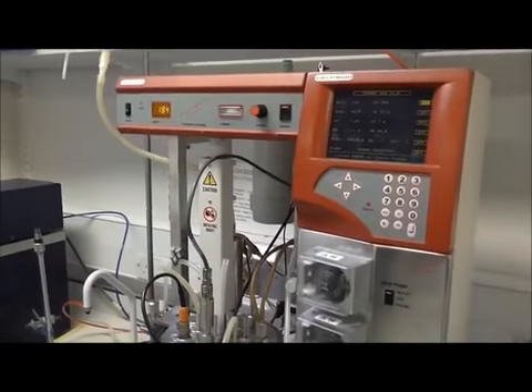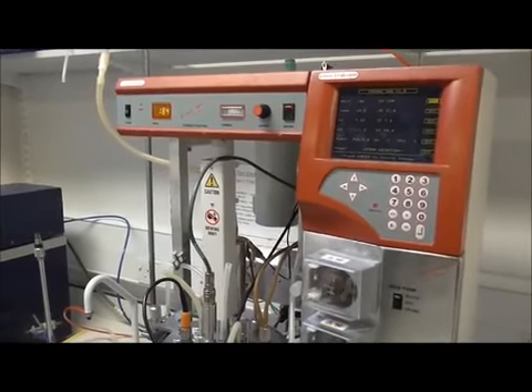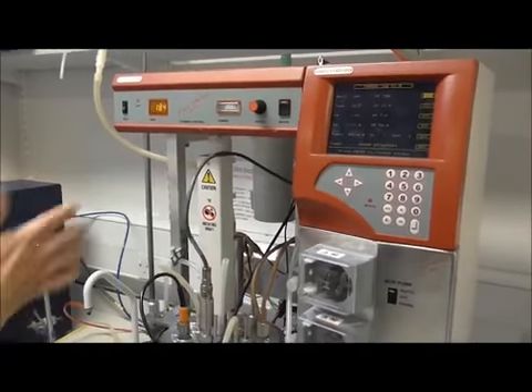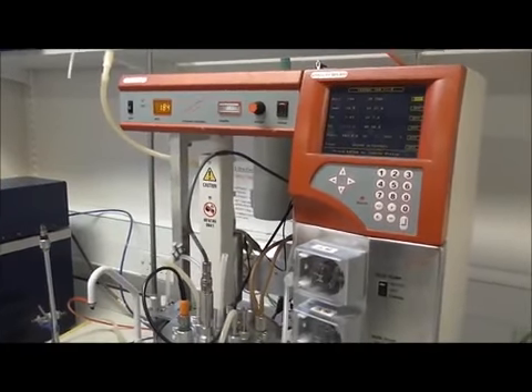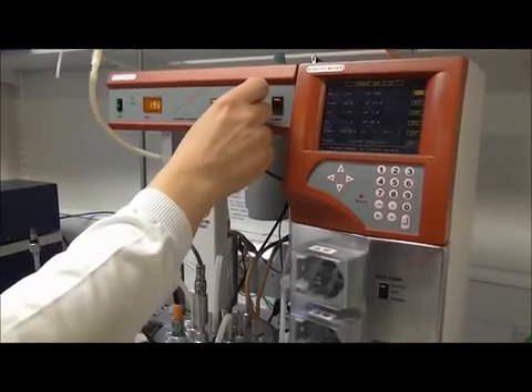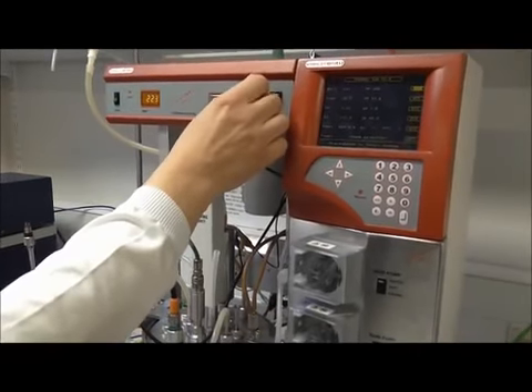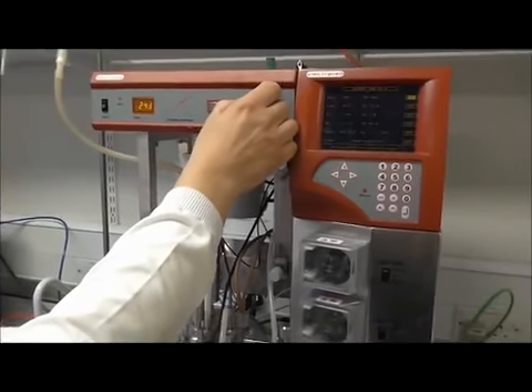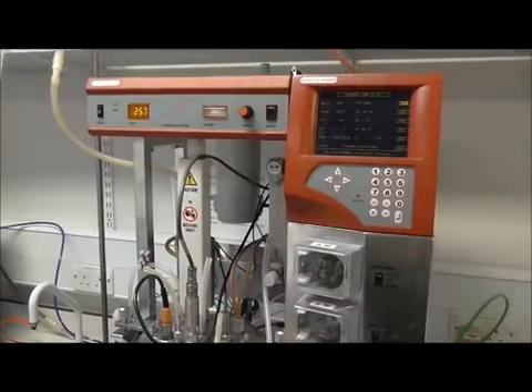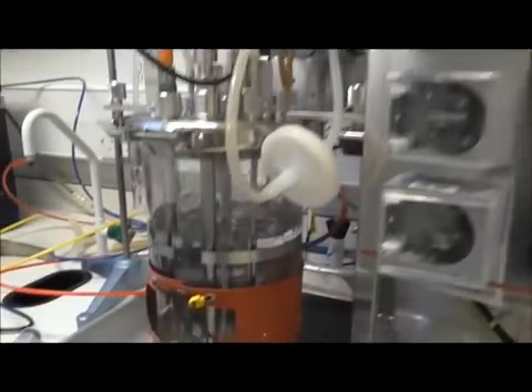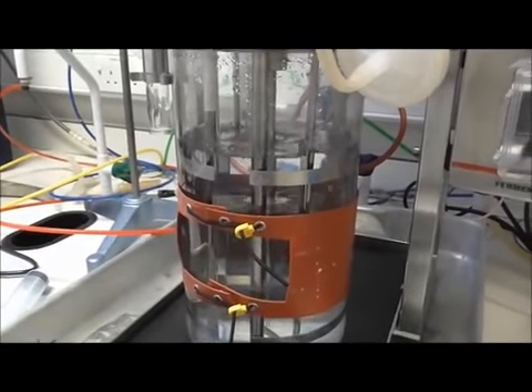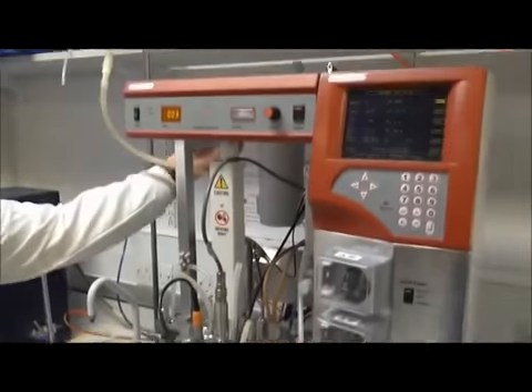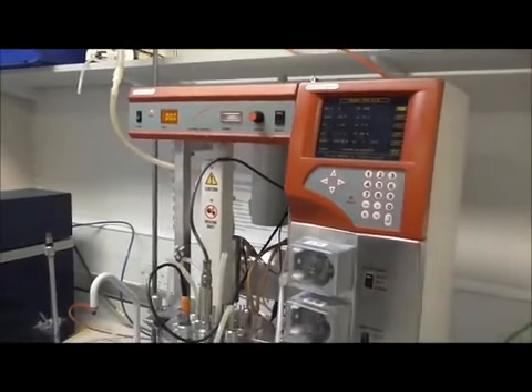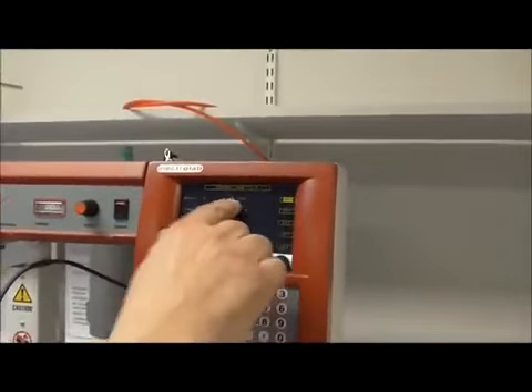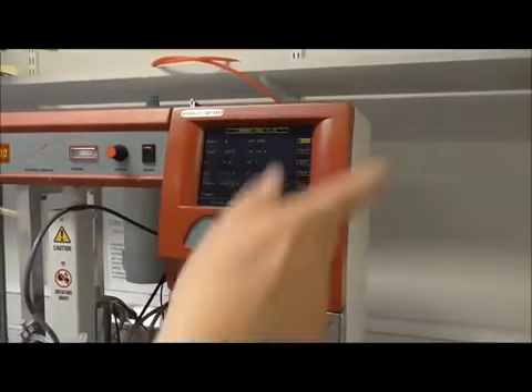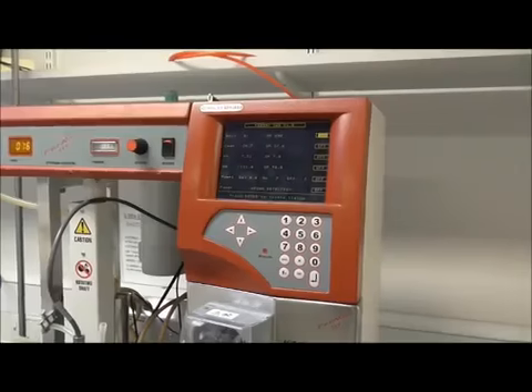Top speed on these is about 1000 RPM. We don't want to do that every day because, as I explained earlier, it does put a bit of a strain on the drivetrain and the motor. But we normally start off around about 200–250 RPM. So we'll just turn that down. Well, we'll pop it onto external control and hand power over to the controller. So we check on here, set point 250, we're off at the moment. To change that to on, we press enter, and off we go.